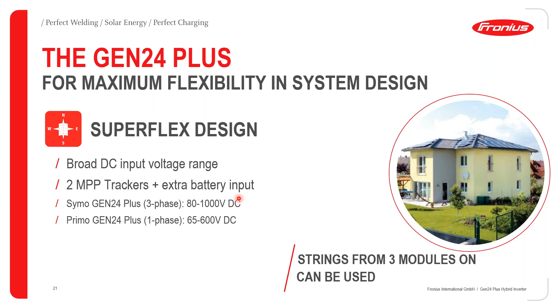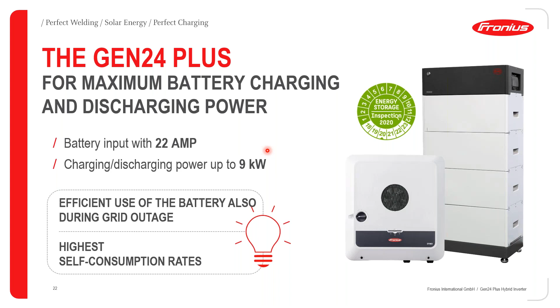The Gen24 Plus inverters are also unique in the fact that you can get maximum charging and discharging power out of the inverter. In this case, we have a battery input or output of about 22 amps and charging and discharging power capacity up to 9 kilowatts for the bigger inverter. So this means that you have efficient use of the battery also during a grid outage, because the inverter is able to take the maximum current or power available from the battery, and therefore this will also significantly increase the self-consumption rates of the Gen24 Plus inverters.